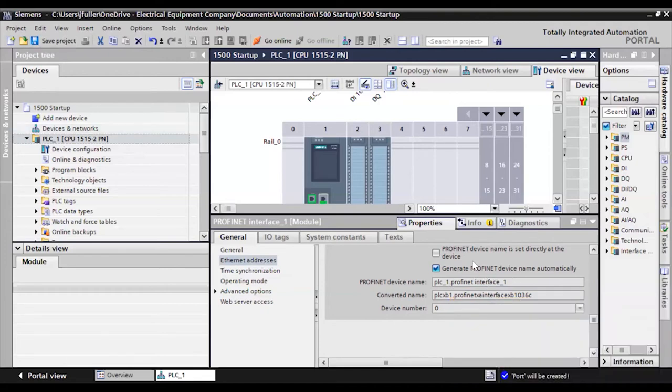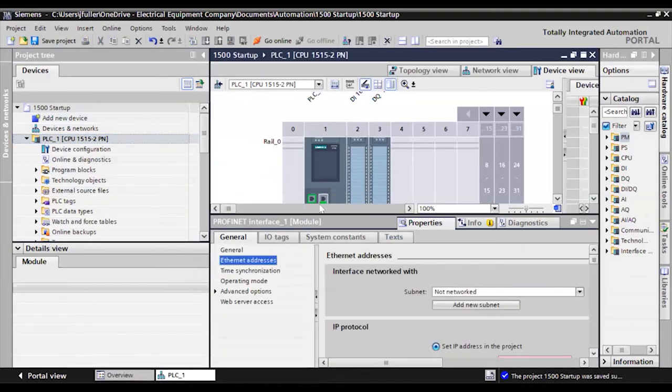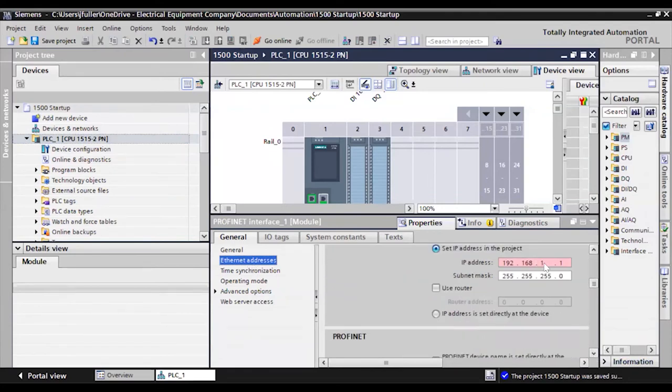Now that I've assigned a new IP address, I'm going to save my project. And we'll see it should pop up and say it was saved successfully. There we go. And now we are going to right click on our PLC and compile hardware and software changes. All right, so we're going to double click here on our Profinet ports, and we're going to bring up the properties tab here in TIA Portal and select Ethernet addresses. And I'm going to scroll down and type in an IP address here.